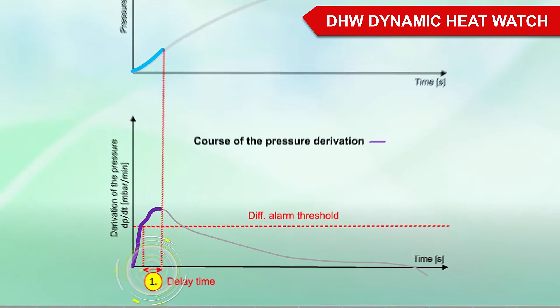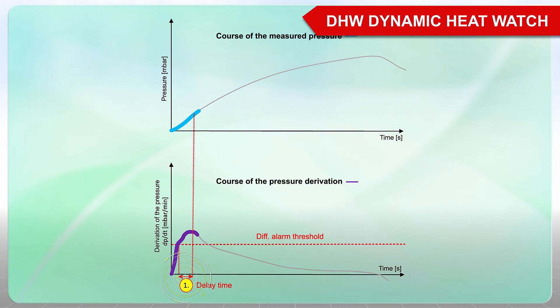First, the pressure gradient is considered. If the rate of rise of the pressure exceeds the configured limit DIFF ALARM THRESHOLD, the delay time is started. If this limit value remains exceeded during the defined time, the alarm verification algorithm is started.